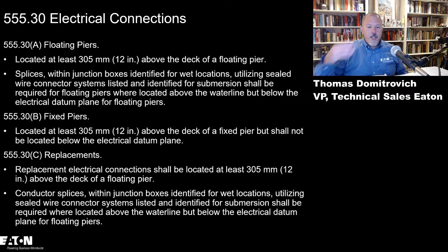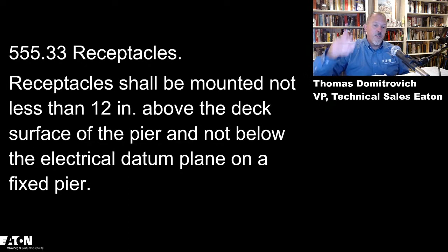And how do you determine what that high water level is? Then they talk about replacements: receptacles have to be mounted not less than 12 inches above the deck surface of the pier, and not below the electrical datum plane on a fixed pier.